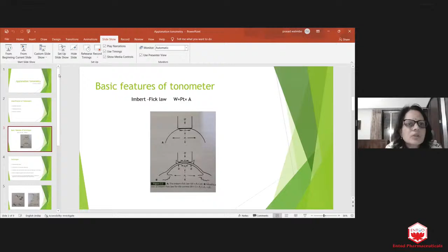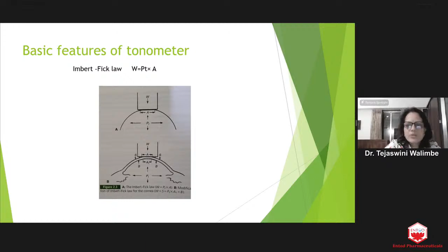Yeah, sorry. So these are indentation, applanation, and non-contact tonometers. So today we are going to consider Goldmann tonometry, which is commonly used, preferred, and near to accurate, near to perfect. So that's why it is gold standard considering the intraocular pressure measurement. The basis depends on the Imbert-Fick law. Means the weight used is equal to the intraocular pressure multiplied by area applanated. But for this formula, the cornea should be spherical, dry, perfectly flexible and thin, which is not the case of a natural human cornea. So this formula has been modified a little bit.